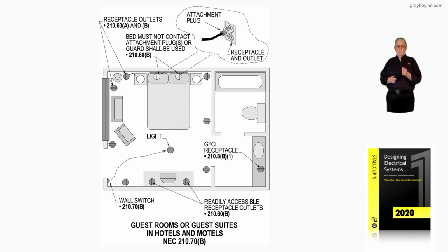Notice the rule, though, for those receptacles if they're behind the bed. Bed must not contact attachment plugs, or guards shall be used to prevent that from happening. And then you see the receptacle outlets in 210.60(A) and (B).